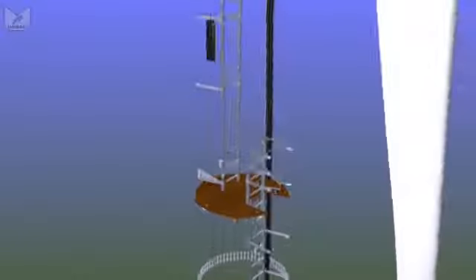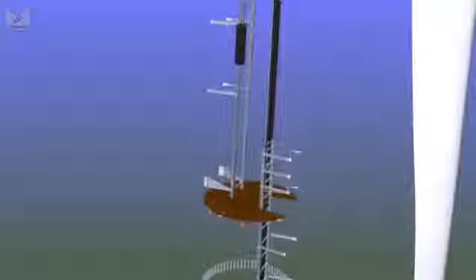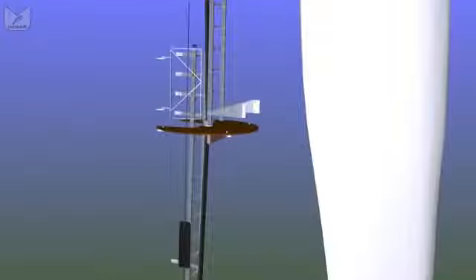But eventually, the main cables stop being attached to the wall and they hang freely in the centre of the tower, so they can twist as the nacelle rotates to face the wind. If they twist too many times, the nacelle will spin itself around to remove the twists.